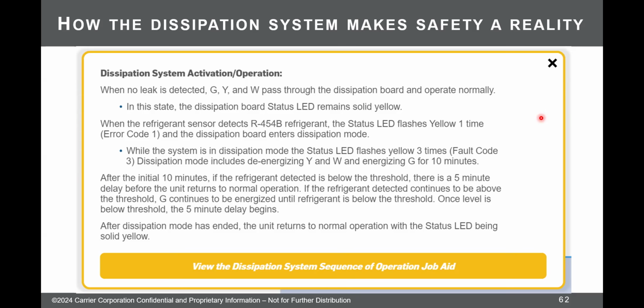I think they're concerned that there'll be a leak in the evaporator coil. It'll migrate down into the furnace cabinet. There might be a hole in the heat exchanger of the furnace. So now it migrates its way to the igniter. And then we try to turn the furnace on, and the igniter will, in fact, go ahead and light it, because that's definitely a hot enough surface temperature to ignite refrigerant. So that's their concern there. So no cooling, no heating if there's a leak.